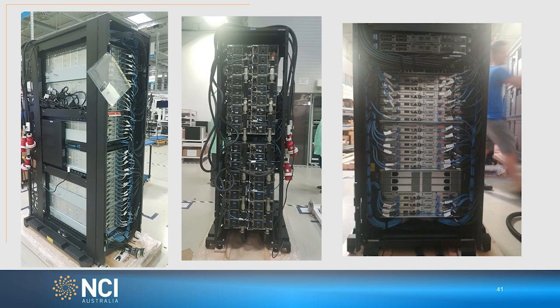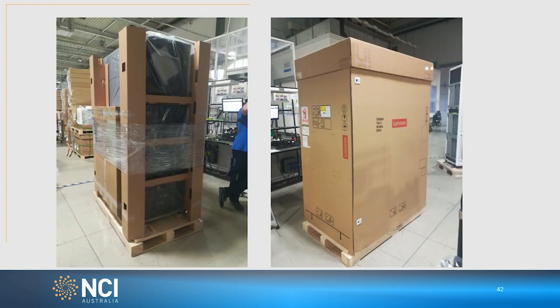Within the factory, they actually build the servers and also construct the racks themselves. They put them together, wheel them around as a complete rack unit, and validate that all the nodes in the rack work. If they don't, they swap out the entire node until they've done all the testing. They then pressurize the entire system with nitrogen to make sure it's watertight, fill it with water in a clean room, run it for two days doing HPL, empty it out, fill it with nitrogen again to wash out the water, and then package it up. So they ship the entire rack ready to go.